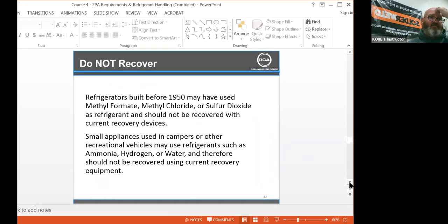Do not recover refrigerators built before 1950, as they may have used methyl formate, methyl chloride, or sulfur dioxide as a refrigerant and should not be recovered with current recovery devices. It also applies to small appliances used in campers or other recreational vehicles that may use refrigerants such as ammonia, hydrogen, or water, and therefore should not be recovered using current recovery equipment.